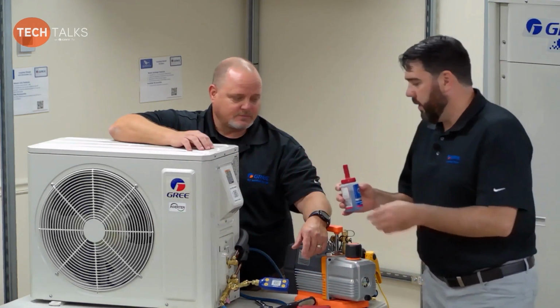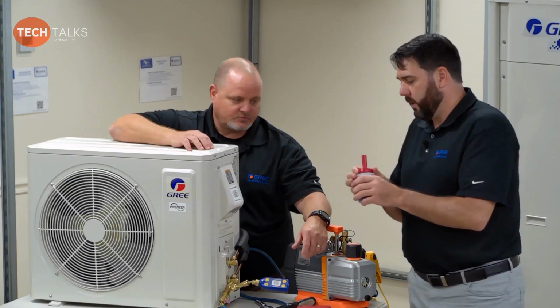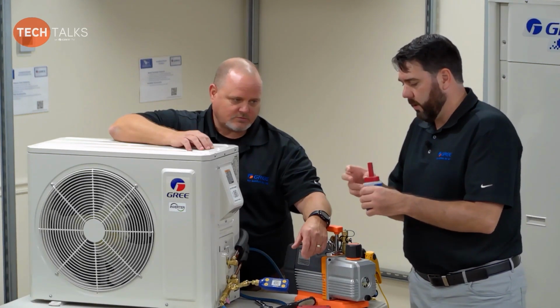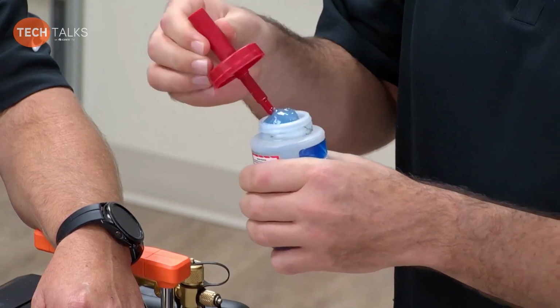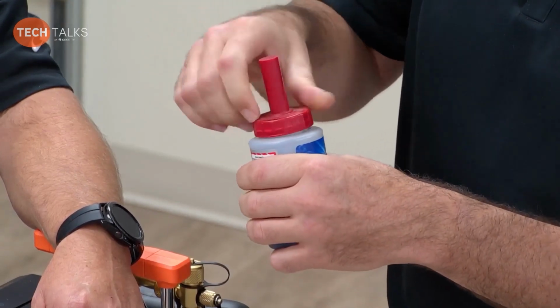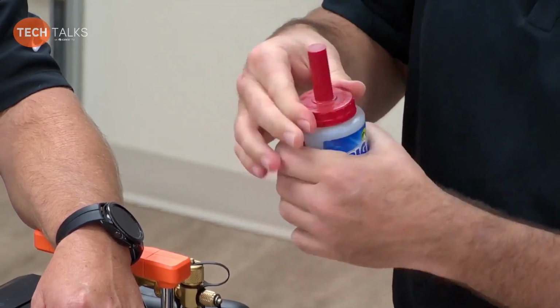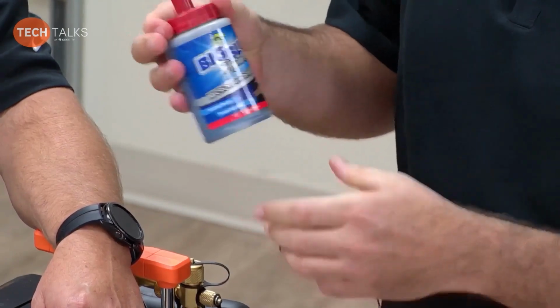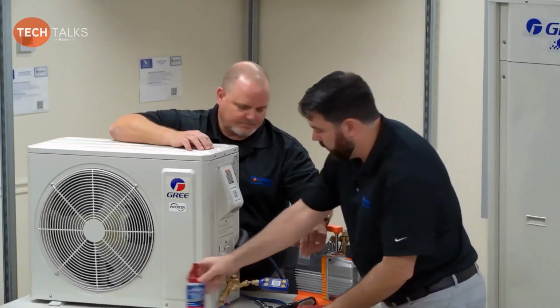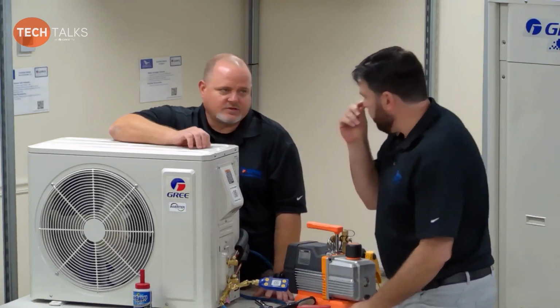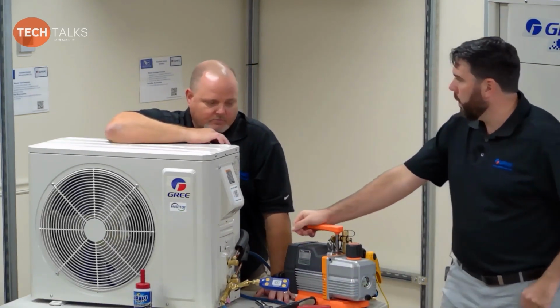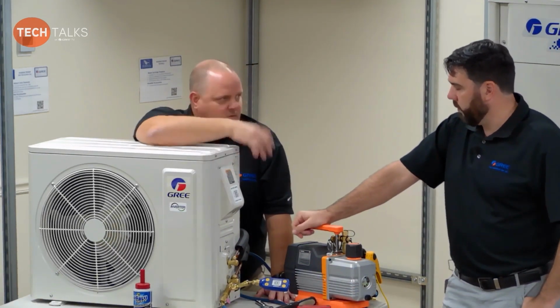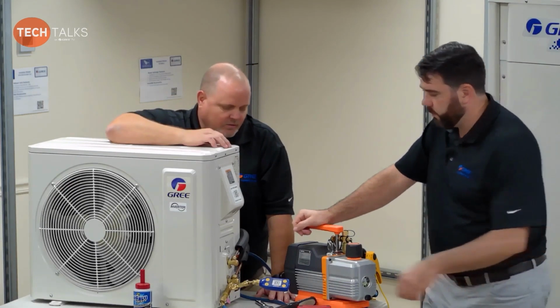And then the other key is once you pressurize it, you're not always going to hear anything. But if you use some good leak detector solution and soap your fittings good, then if anything's there, you're going to find it. And then the other test that you're going to do is just by holding vacuum. So once we get past this stage, now we're going to go into evacuation.